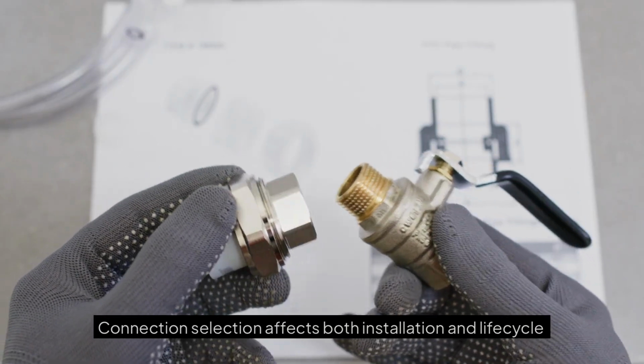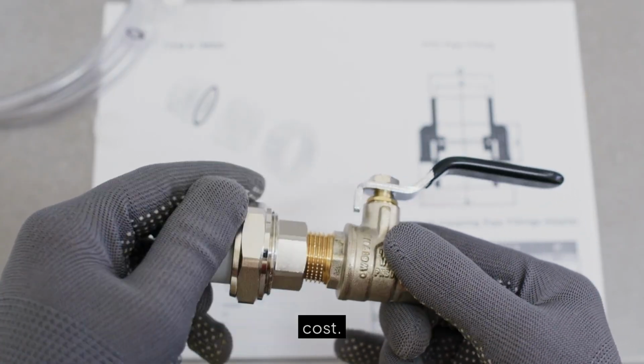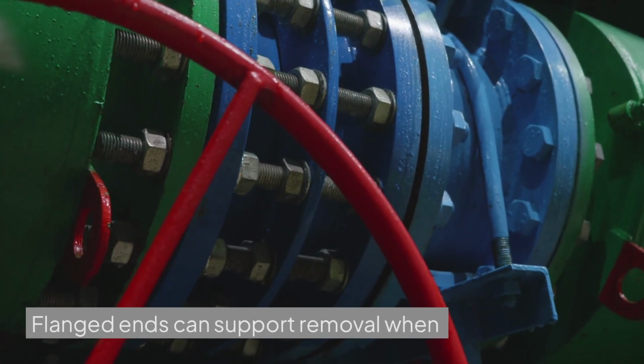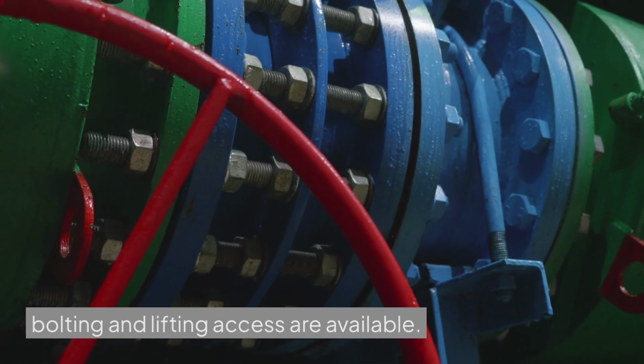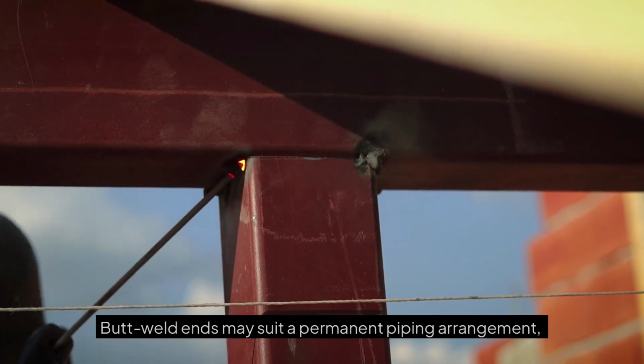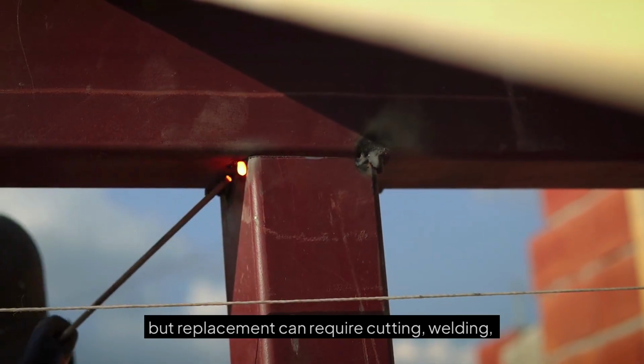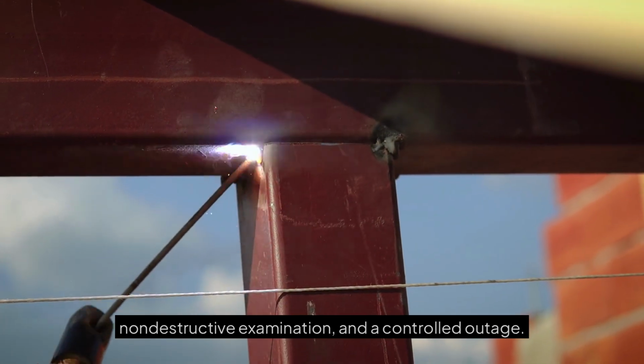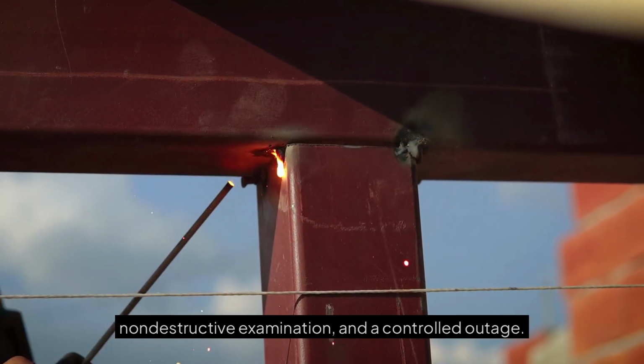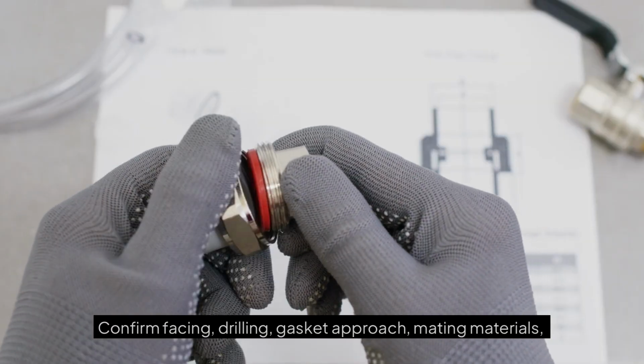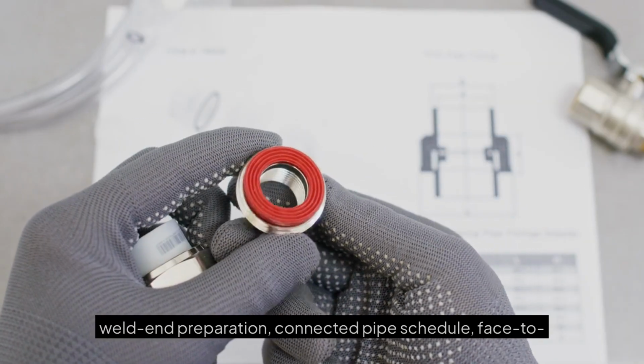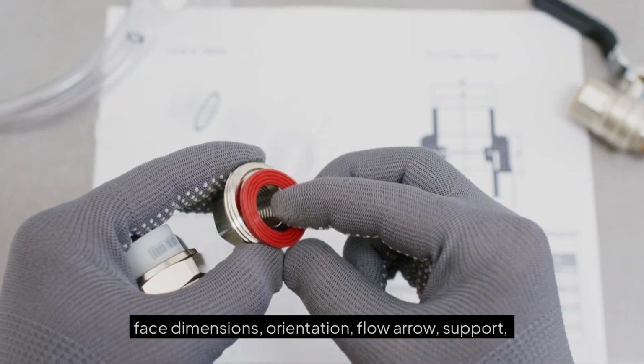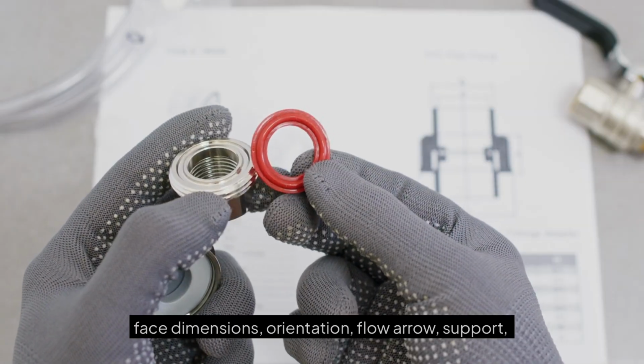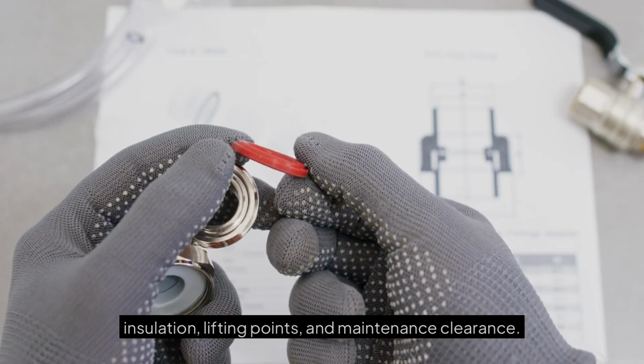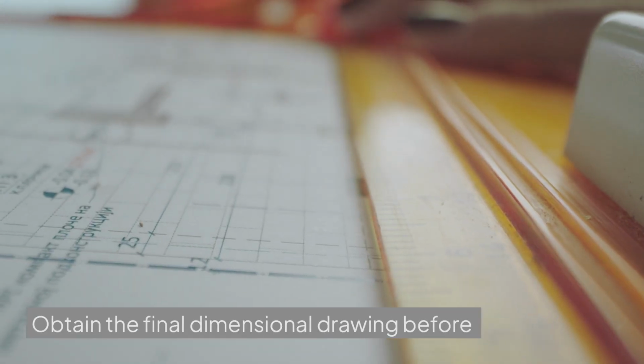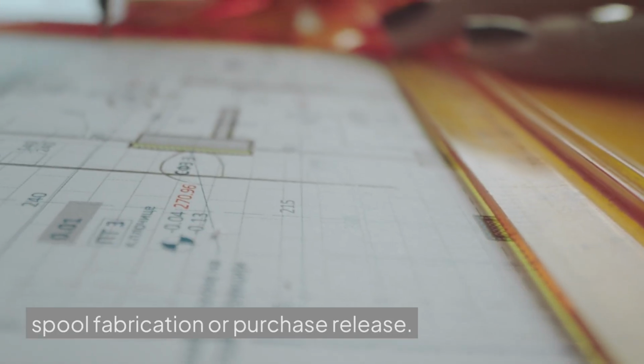Connection selection affects both installation and lifecycle cost. Flanged ends can support removal when bolting and lifting access are available. But weld ends may suit a permanent piping arrangement, but replacement can require cutting, welding, non-destructive examination, and a controlled outage. Confirm facing, drilling, gasket approach, mating materials, weld end preparation, connected pipe schedule, face-to-face dimensions, orientation, flow arrow, support, insulation, lifting points, and maintenance clearance. Obtain the final dimensional drawing before spool fabrication or purchase release.